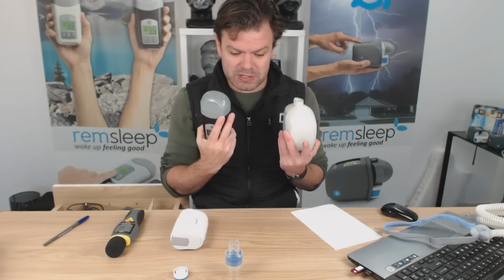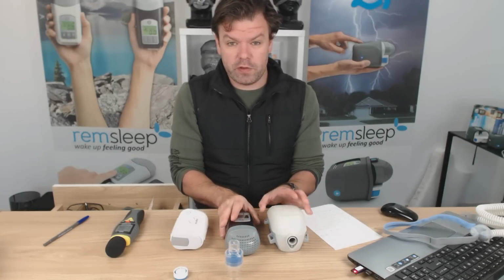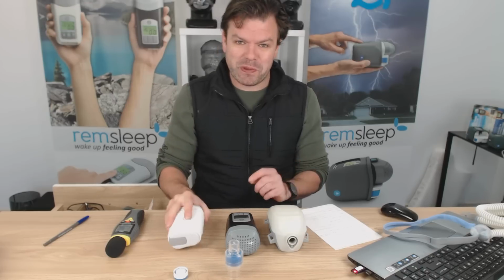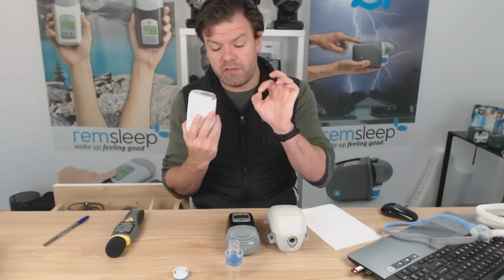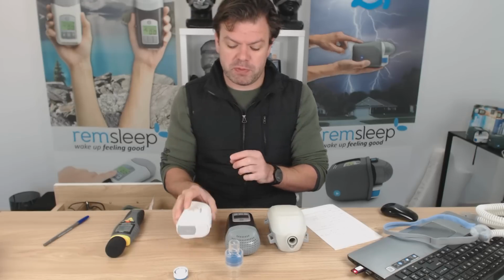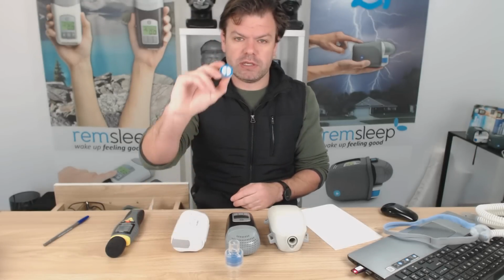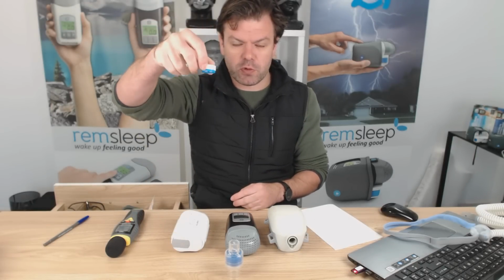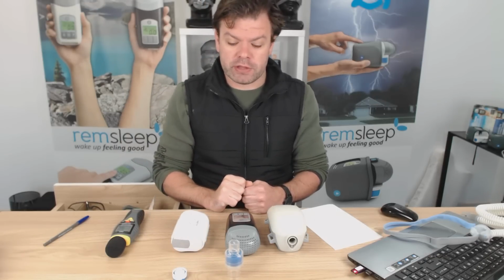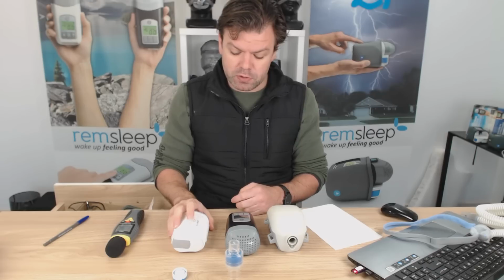One note before leaving - with these two machines, you can use any mask, since they have standard tubing that works with any mask. With the ResMed, you can only use the P10, the N20, or the F20, which are specifically modified versions of those masks that come with a special connector so you can screw in these HME filters. That's a really important note to make.